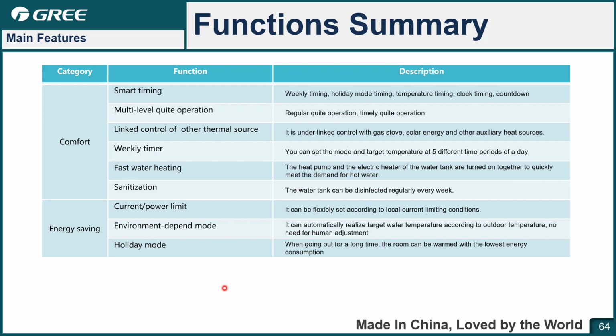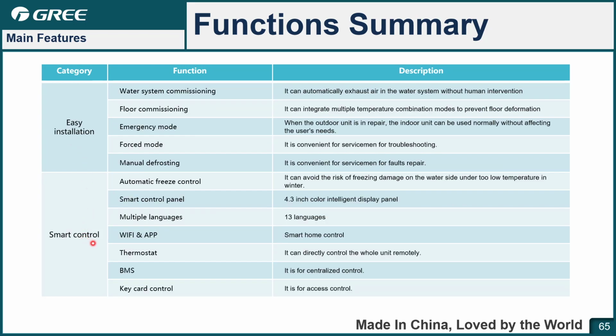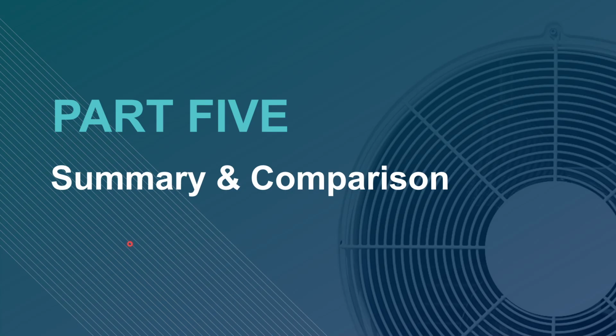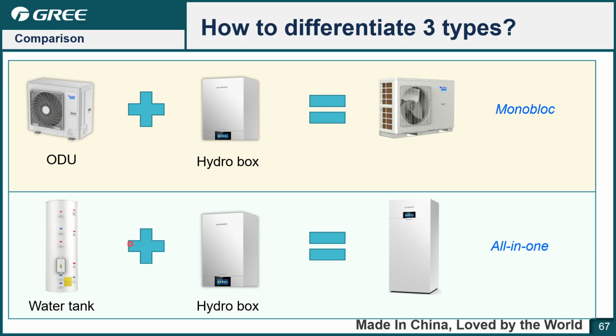Here is a summary of the function settings, such as comfort, energy saving, installation, smart control. That's the summary table. Okay, so the last part is the summary and the comparison between these 3 types. How to differentiate the 3 types: the split, the all-in-one type, and the monoblock. For the split type, the outdoor unit, water tank, and the hydro box are independent, right? If you put the hydro box into the outdoor unit, then you get the monoblock. If you put the hydro box into the water tank, integrated together, then you get the all-in-one. That's how to differentiate the 3 types.